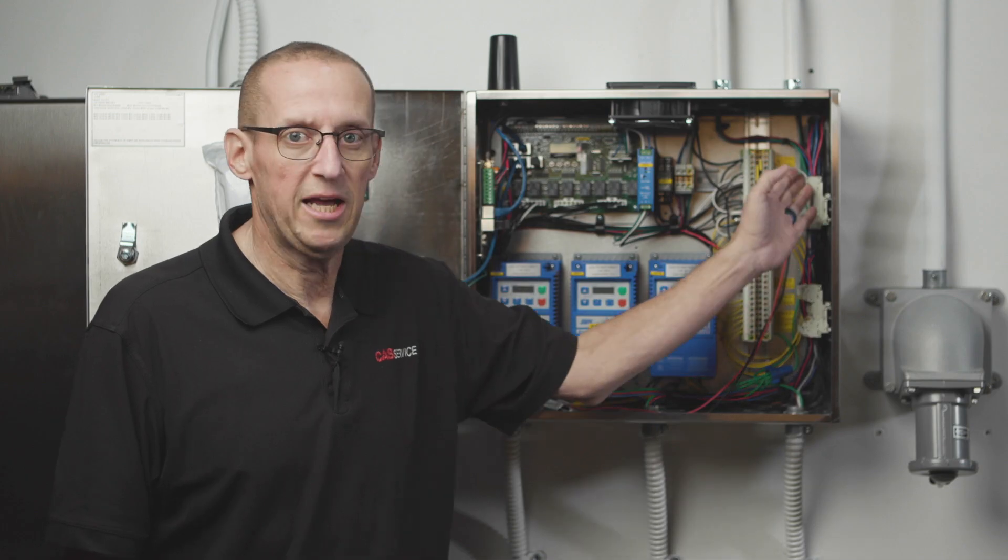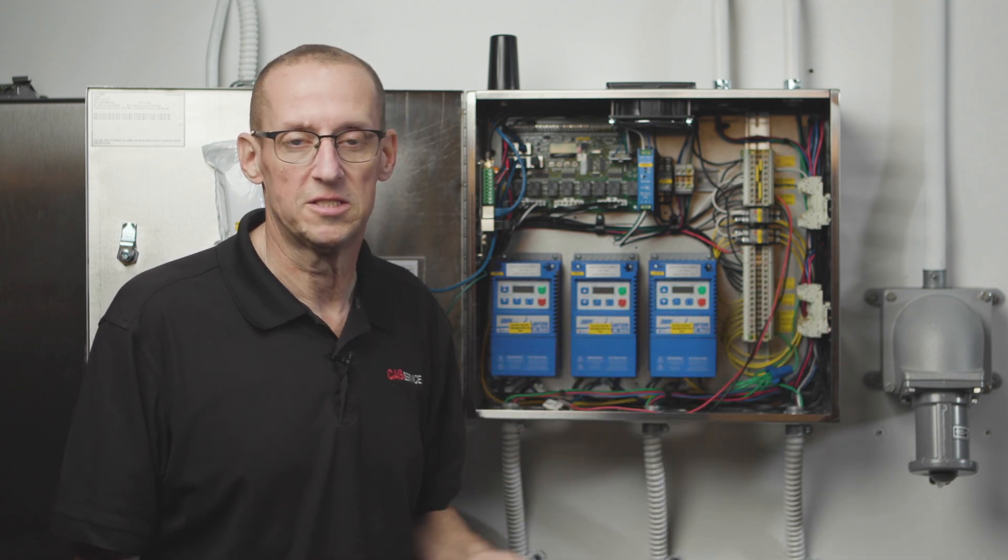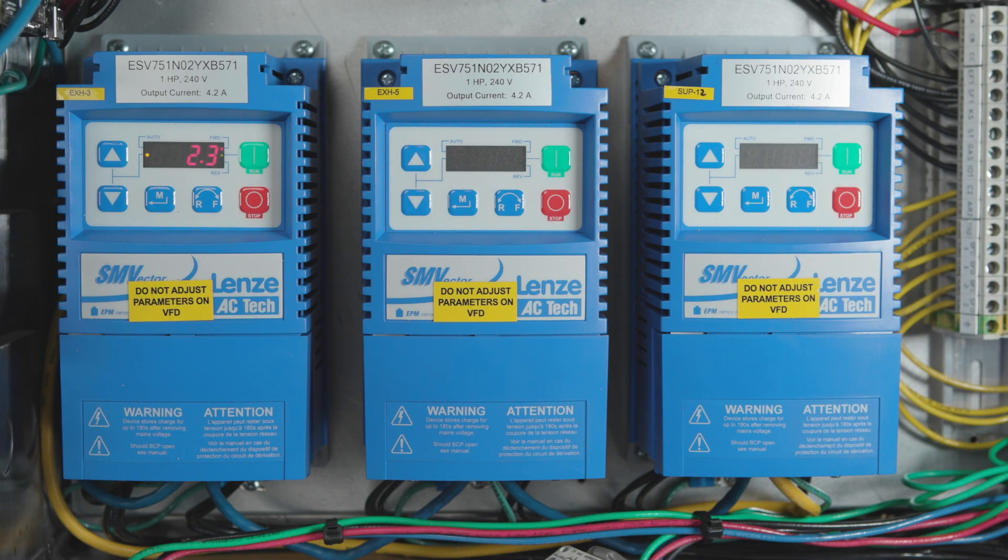If you mix up line and load here, when you turn on the breaker, it's going to short the VFD instantly. It's going to have to be replaced. With these quick disconnects unplugged, when you turn on the breaker, one of two things is going to happen.